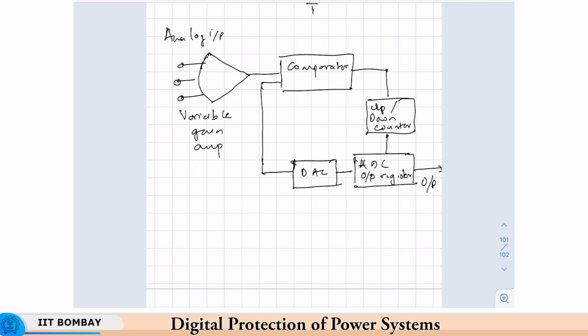Okay, so you get the analog input, you compare, you set the values, the digital counter up or down, then you convert it back to the analog value and compare if there is an error. If there is an error, you go back to this loop and keep incrementing or decrementing it till the error is reduced to whatever is the design threshold, and once that is done, then you can get the output.